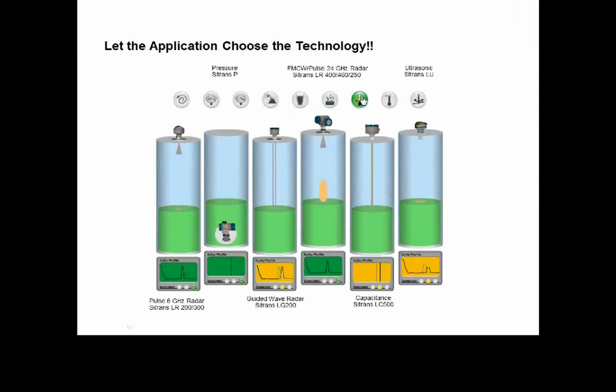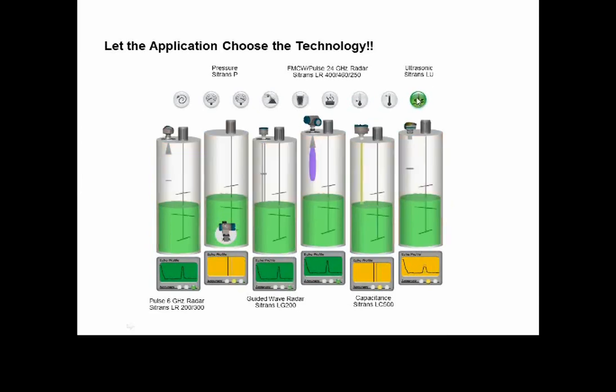We can look at low temperature applications, in which case we look at the equipment itself, the process connections, and the materials of construction based on handling very cold processes, or conversely, very hot temperatures. And then we have challenges with agitation. I can't necessarily use a guided wave radar in a tank where there's an agitator, because I'll be hitting the sensing rod and causing some problems. So the main point here is we try to let the application choose the technology.